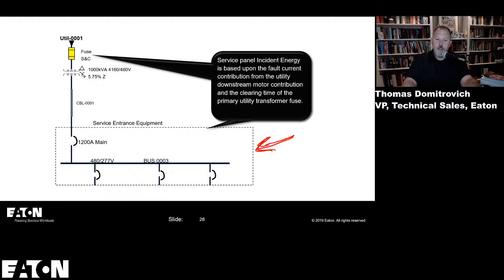panel board. So if you're working in this panel board and you're doing the justified energized work, or again, if it's a service entrance, you've got to call the utility to kill power. You may try to turn the breaker off here, but in reality, because of line side propagation, because of that plasma cloud that can occur inside this equipment, you could go phase to phase to phase on the line side of that primary breaker, which would mean the only clearing time is based upon that primary overcurrent device on the primary of that transformer, because that's your next upstream overcurrent device.